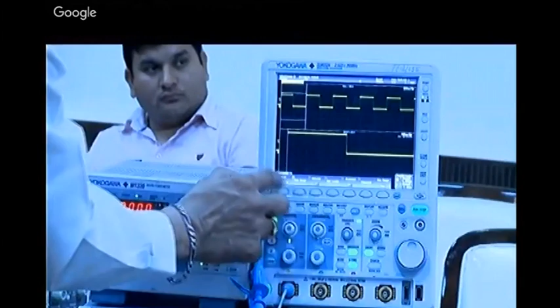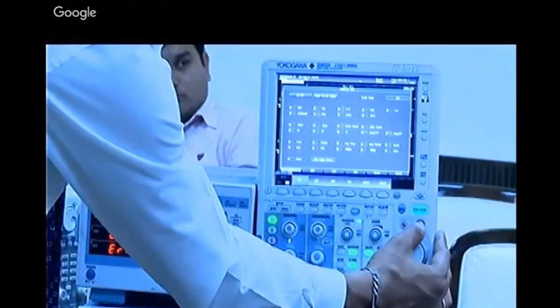Coming to measurement, there were around 20 measurements simultaneously - you can see which channels and what parameters you want, like maximum value, RMS value, or for a sinusoidal or repetitive signal, the pulse count. You can also see frequency or rising time - all these values will come here as automatic measurements.